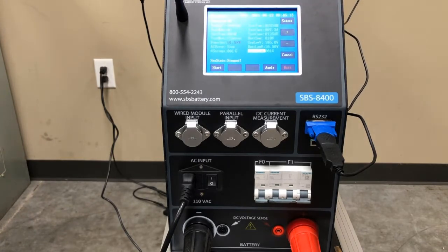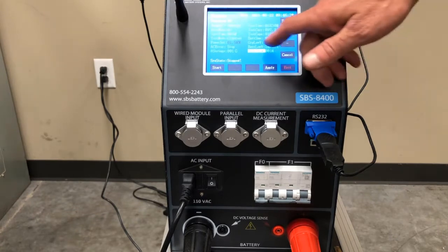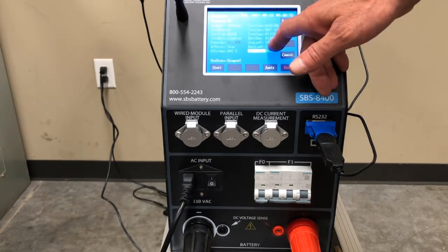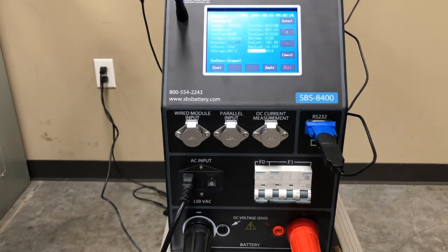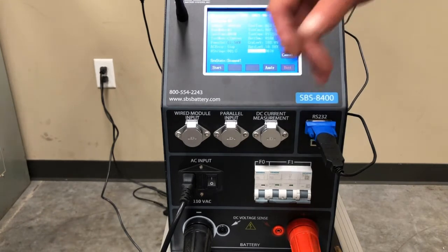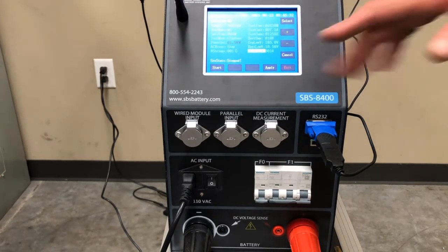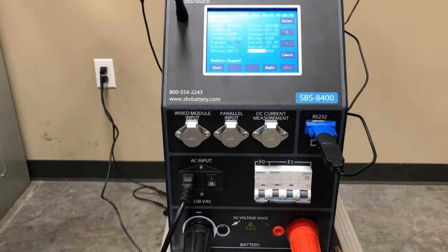My number of battery lows is how many batteries have to hit that 10.5 level before the test automatically stops. What happens in capacity testing is people will set this at 1, and as soon as the first battery hits 10.5 volts, it stops the test. What I've done is I've measured the capacity of that one battery, but I haven't measured the capacity of the string as a whole, or all the other batteries in that string.